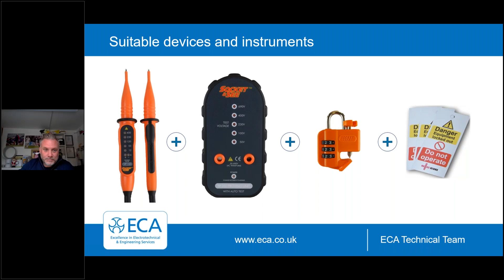Safety also applies when we're going to turn things back on, and a lot of accidents actually happen upon re-energization. So it's ensuring the removal of all locks and ensuring there's no live parts that could cause risk - equipment's been safely terminated, the covers are all back on, there's no bare ends, nothing live, no exposed live parts.